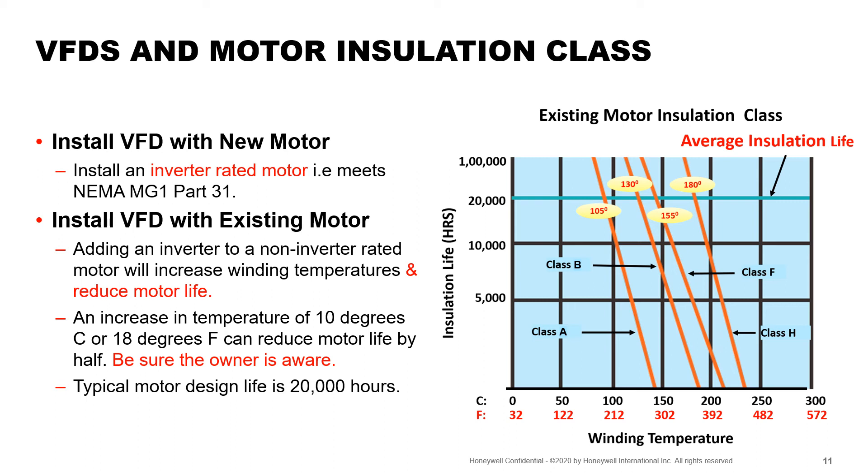Every motor has a nameplate and on it you will find the NEMA insulation class. The most common classes of insulation are A, B, F, and H. The greater the insulation class, the greater the temperature the insulation can withstand without degradation. Class A is found on older motors and has the lowest tolerance to heat. Class B motors are commonly used for fans and pumps. Motors with class A or B insulation may fail prematurely when paired with a VFD, especially if set up to run at lower speeds. Motors with insulation class F or H are well suited for applications with VFDs. These are called inverter duty motors. The best thing to do is to replace a non-inverter rated motor with an inverter duty motor when the VFD is installed. However, the owner may choose to upgrade with VFDs first and replace the motors with an inverter duty motor later when the motor fails.